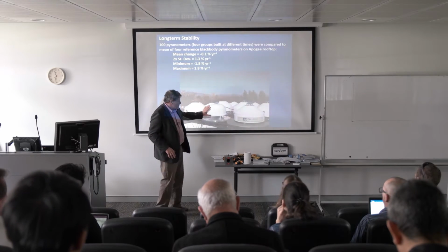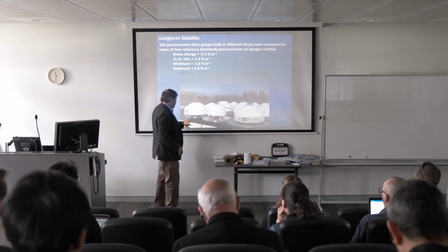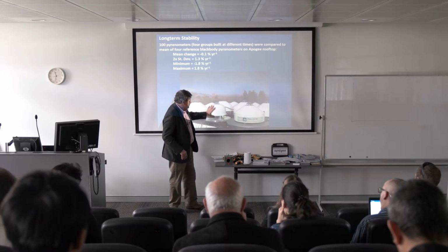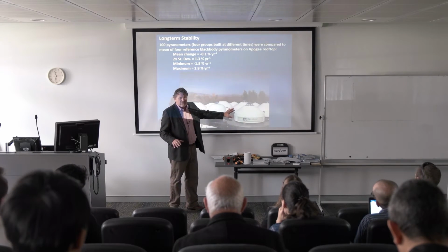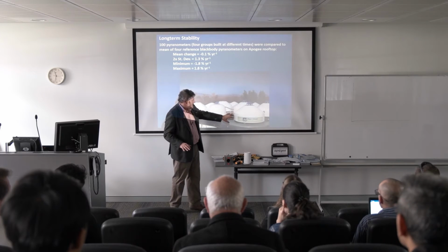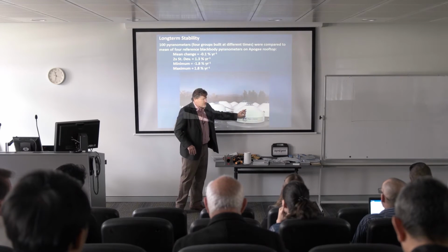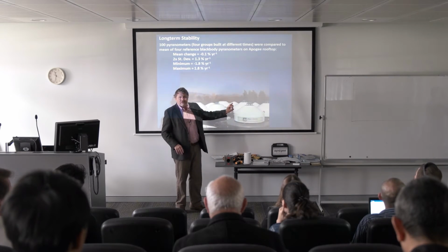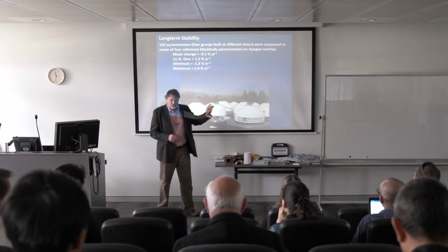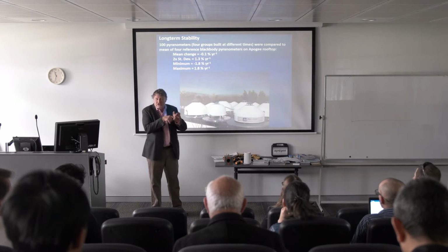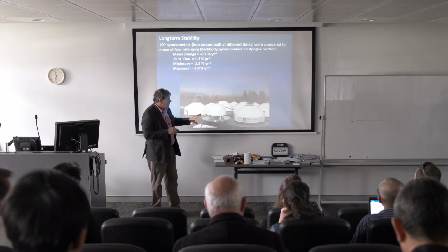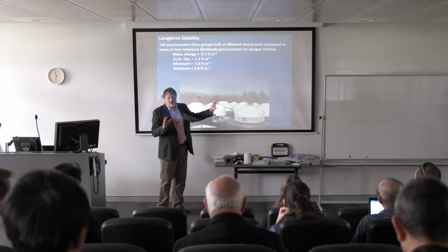If you look at high-end sensors, and now unfortunately we can't quite see them in this picture because these are all shielded and aspirated to get peak accuracy, but you see a little side port with desiccant in the port, and it's often designed to change color. So if water vapor gets inside the sensor, you see that change.